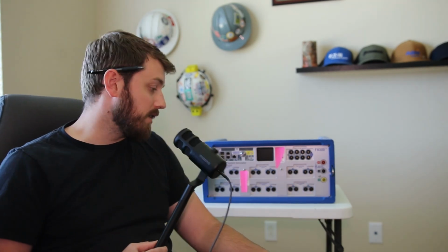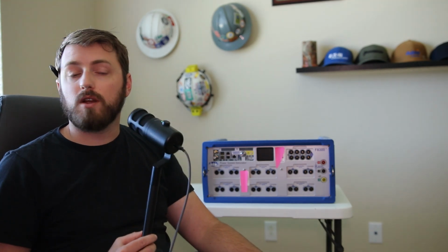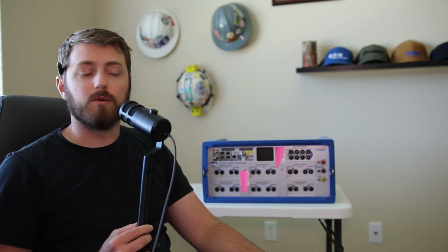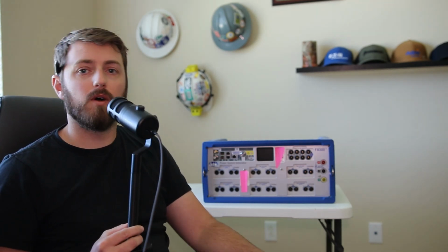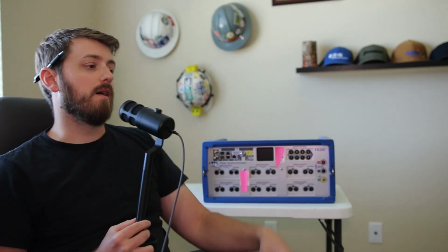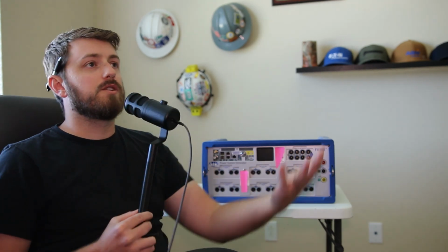I have, at this point, a couple other gripes with it. I was running Protection Suite, and in the troubleshooting process, a Doble rep told me I had to upgrade from version 5.3.1 to 5.3.2 just to rule that out. Then I also had to update the firmware in here, which isn't the end of the world, but it wound up being like an hour-long process to do in the field. That chews up time on a job, having to do all that troubleshooting. So that was really annoying, and it wound up not even resolving my issue. Just another complaint about running an immature product out in the field when you're on a time crunch. So that was super annoying.